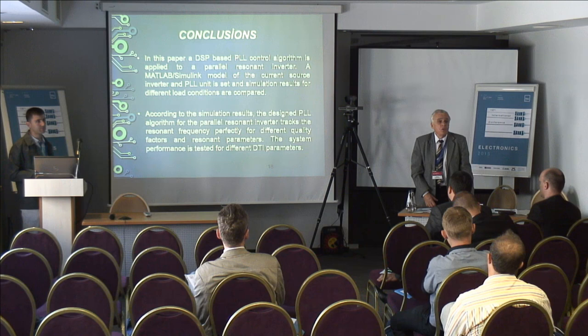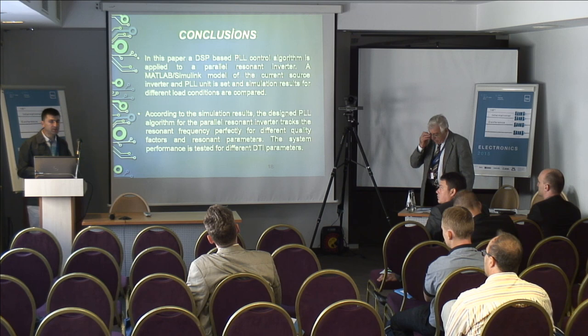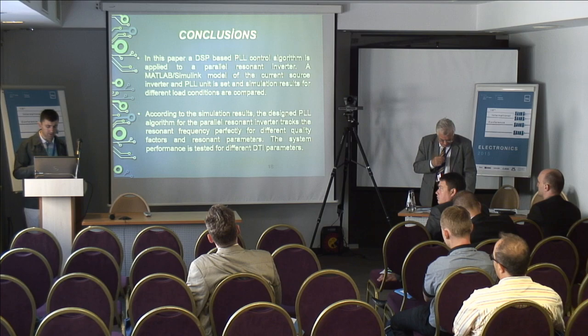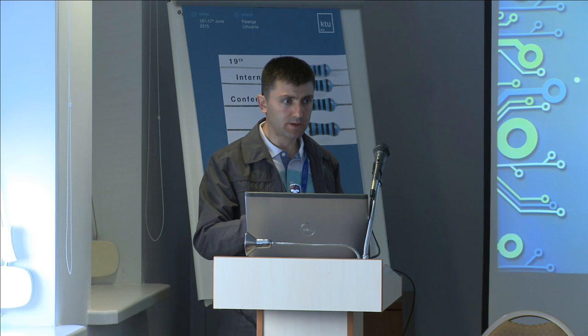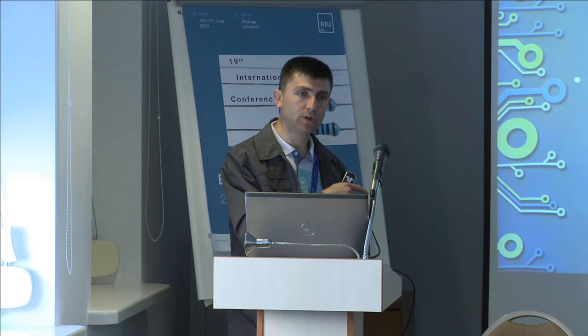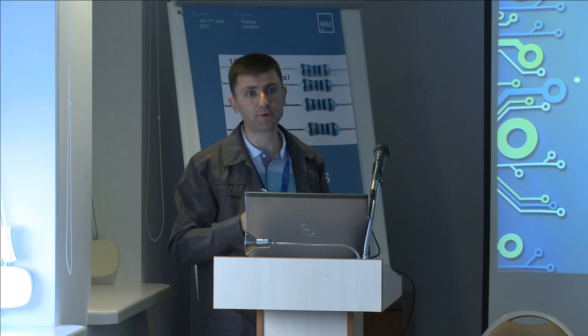Question, please. I wanted to ask, what was the frequency of your PWM signals? We start with an initial frequency and we can choose it. It is not a problem for us. After that, the initial frequency starts to drive the MOSFETs according to the output voltage sensor. We compare the MOSFET signal and the output voltage, and it increases or decreases according to the resonant parameters. And it is about 60 kilohertz.